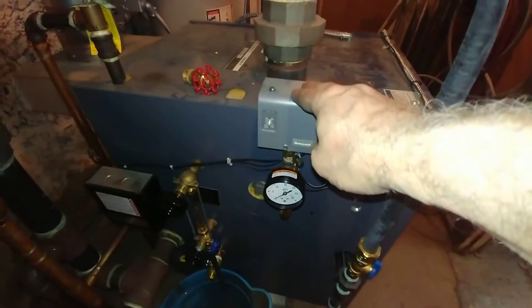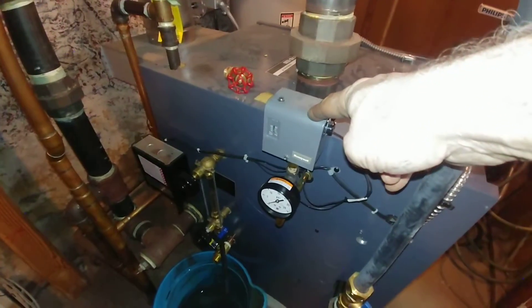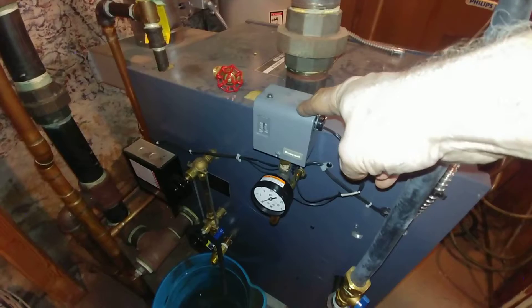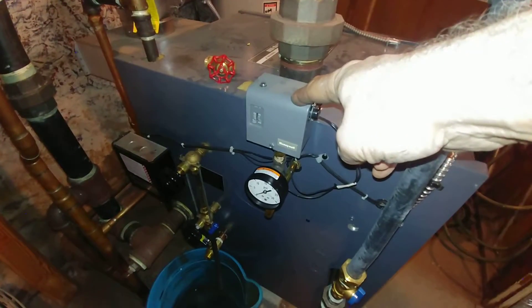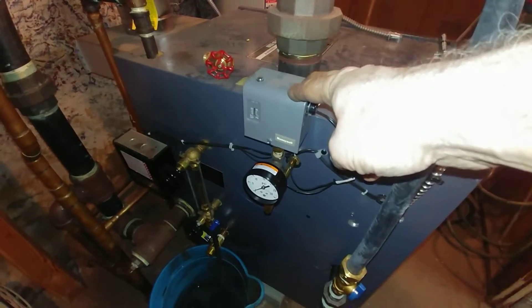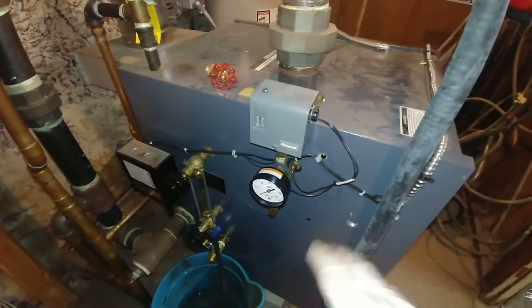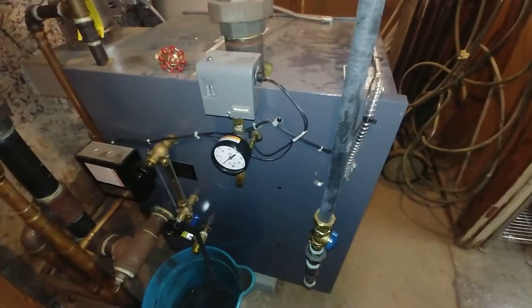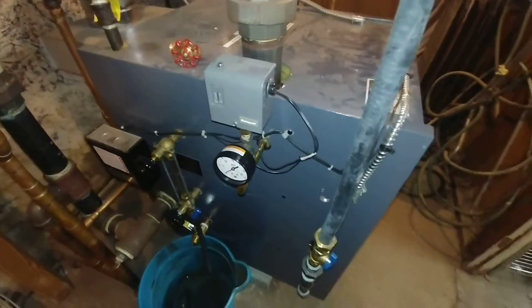The Pressuretrol was set at its lowest setting, but the trouble with this particular Pressuretrol is that it was way out of calibration — it was tripping off at around four or five pounds. We had to tweak it so that it shuts down at the lowest pressure possible, which is a pound and a half, as it's designed to do.